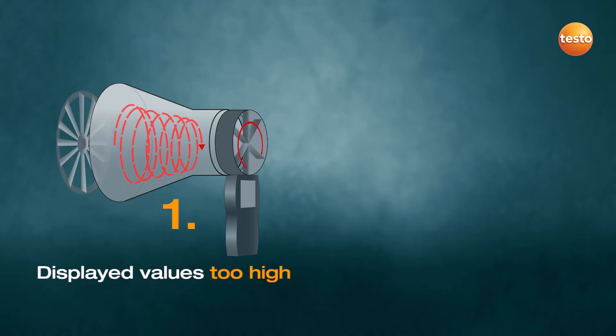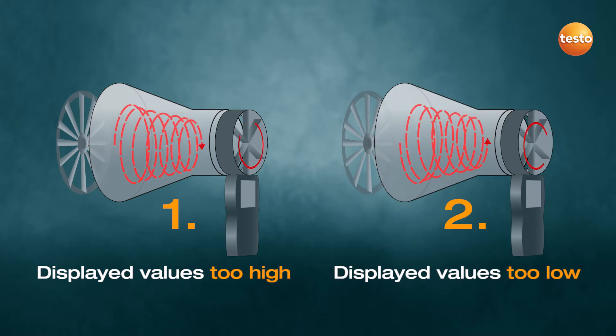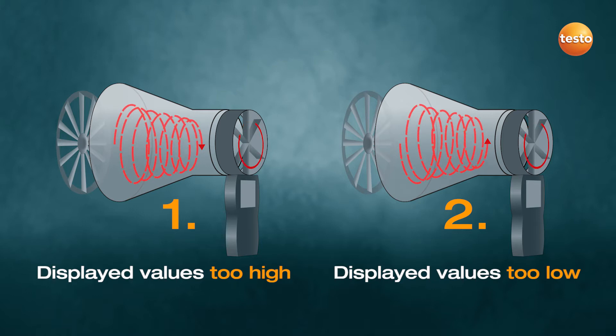Let's take a closer look at what happens. First: the direction the swirl rotates is the same as that of the vane. The flow hits a larger cross-sectional area of the individual blades of the vane, making it accelerate too fast. Second: the direction the swirl rotates is the opposite to that of the vane. The flow passes between the individual blades of the vane, meaning it doesn't accelerate properly. Result: an inadequate flow velocity is displayed.